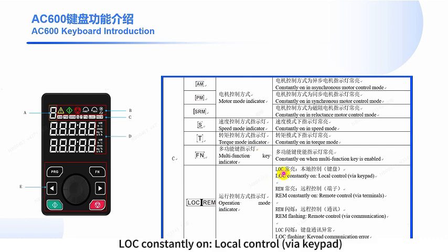LOC constantly on. Local control, via keypad. REM constantly on, remote control, via terminals. REM flashing, remote control, via communication. LOC flashing, keypad communication error.